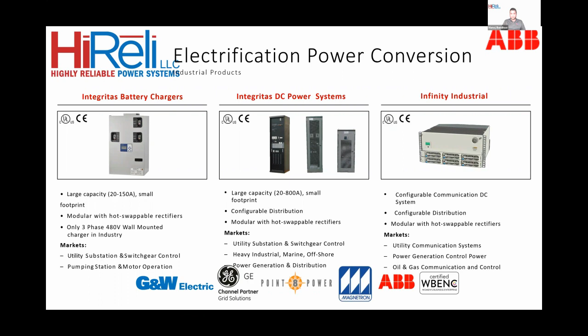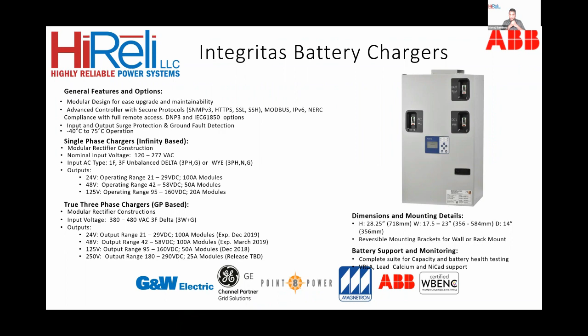So we'll talk a little bit about the wall-mounted system. It's offered in a modular design with an advanced controller with secure protocols. There's single phase and three phase input AC, with specified outputs in DC. An important thing to note is the footprint, very compact, very small, because of the switch mode type of design, which allows for a much smaller footprint.